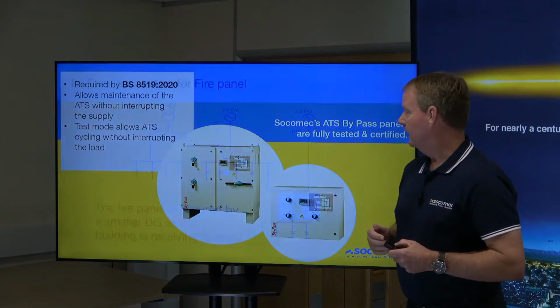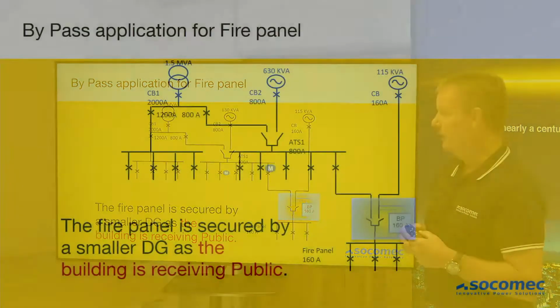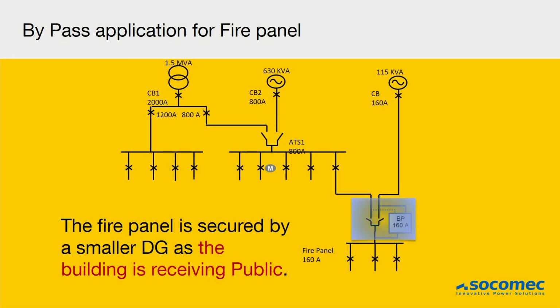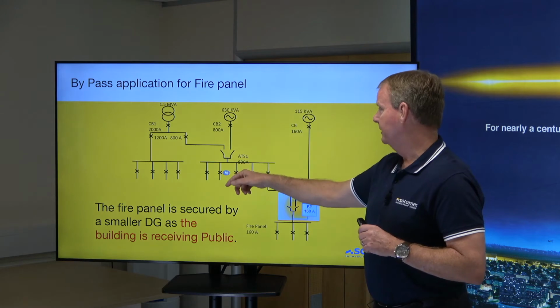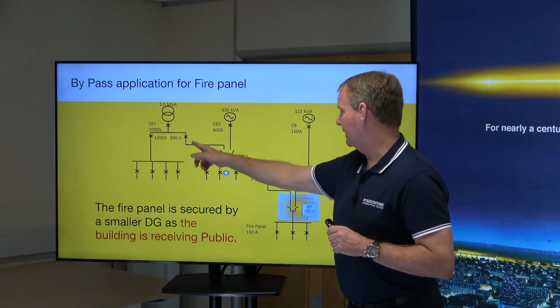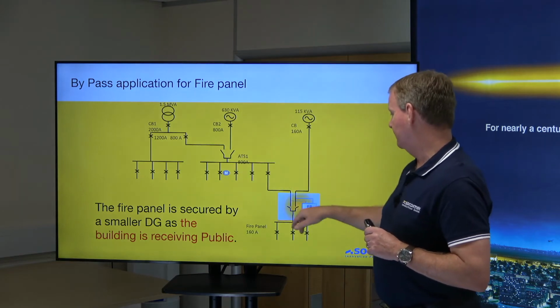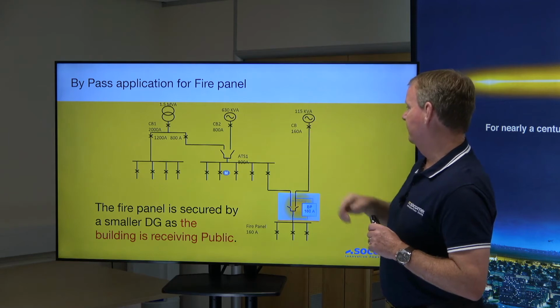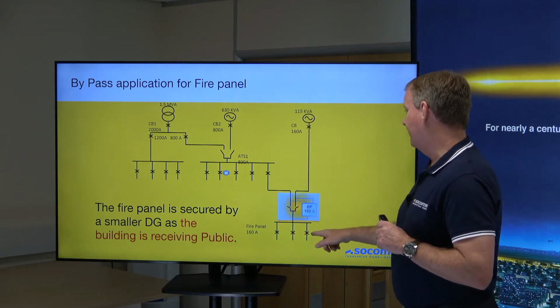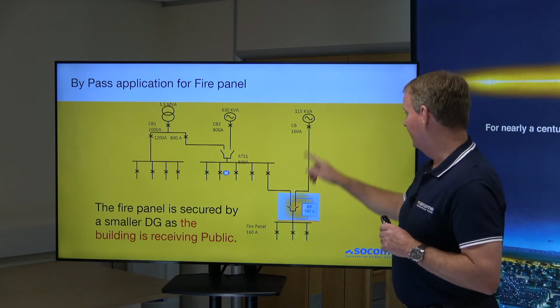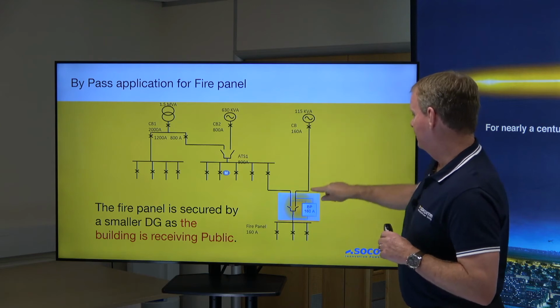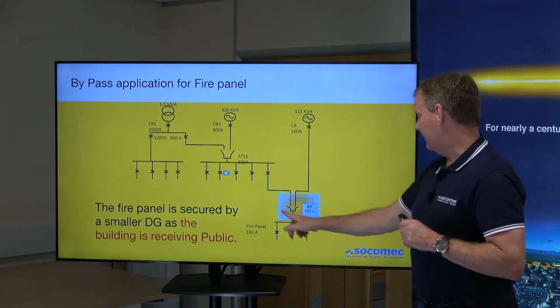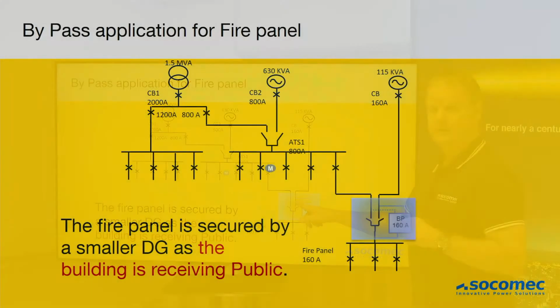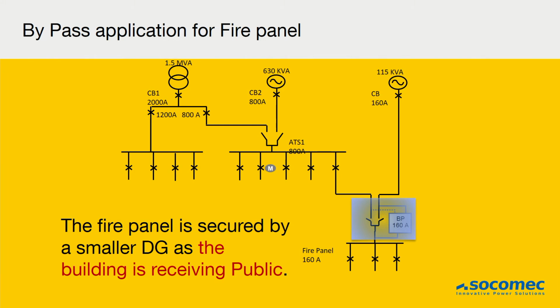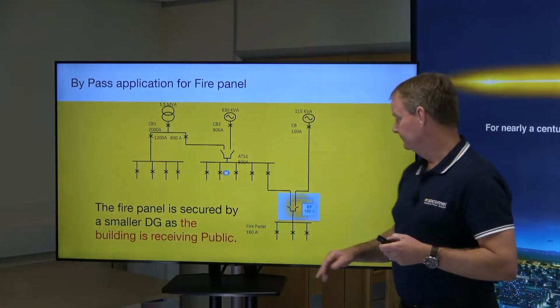Okay. Here's an image of a drawing for a typical bypass application for a fire panel. You have the main supply. You have a secondary source fed via a transfer switch. Normally, obviously, the secondary supply is not the same level. So here, in this case, you would have the essential, not essential, and then essential, and then you have a third source here for the generator, which is also fed as a backup to the fire panel. So if this is on and then it's fed through here, if that fails, the third source comes down through the transfer switch. And here you can see in the bypass area, you have another line that goes around the bypass, which allows you to transfer power if required, if the ATS is out of service or for some reason it fails. So as you see it here, okay?